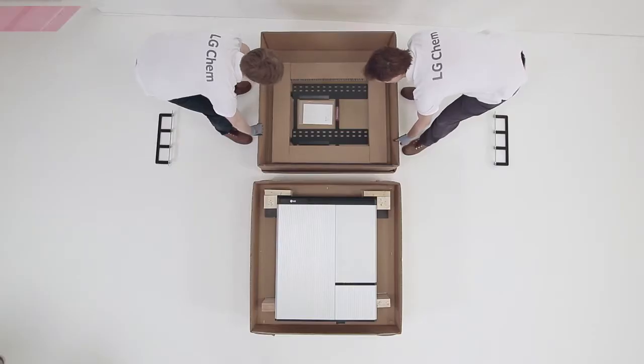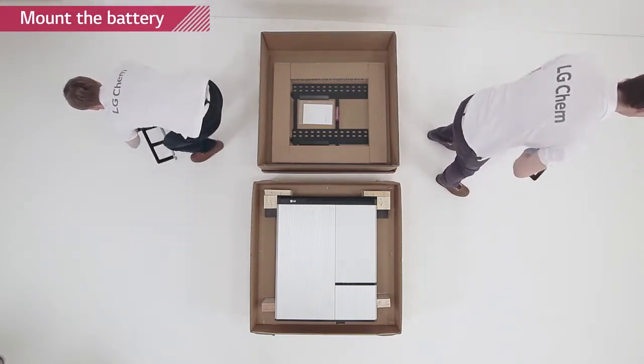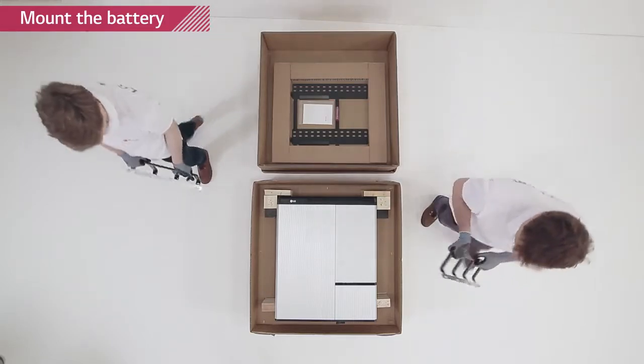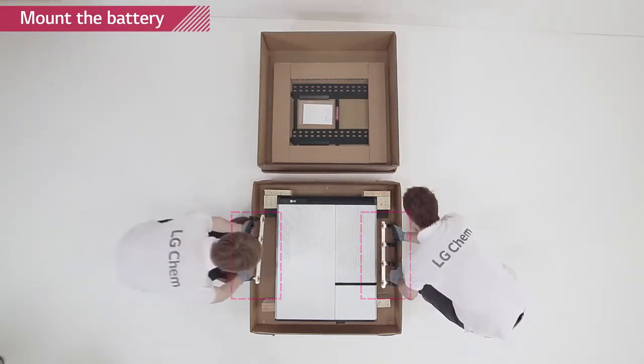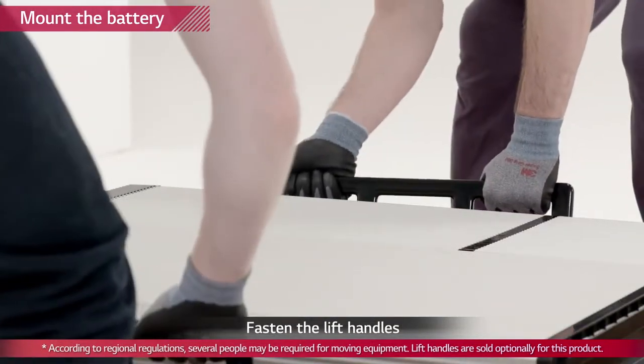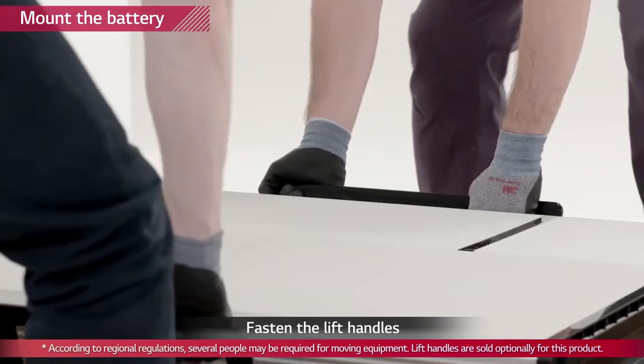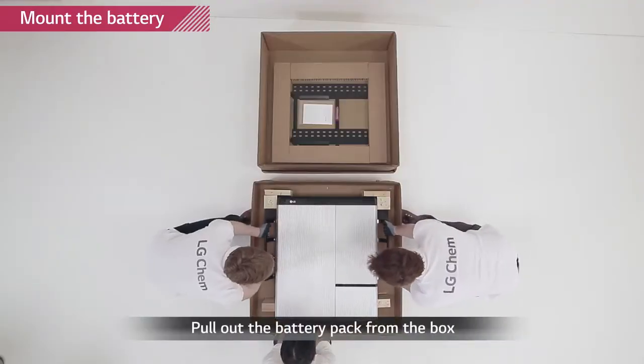Attach the lifting handles to the hex socket screws located at the back of both sides of the RESU pack. Lift the battery pack using the handles. Handle the RESU10H carefully as it weighs about 100kg. Note that the wall on which the battery pack will be mounted must have the capability to support weight over 150kg.